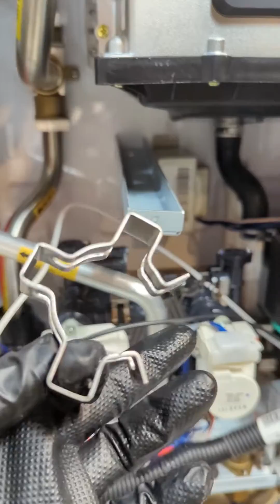That side goes to the domestic heat exchanger. This is the clip for that, and that's for the heating side, going back to return. Okay, so you've unhooked those. If you want to change the whole system, this one is for that. If you just want to change the motor, you basically unscrew, not unscrew, but unclip this to take it out. There's a clip behind it right there. See that? That's the clip, the only thing holding it.